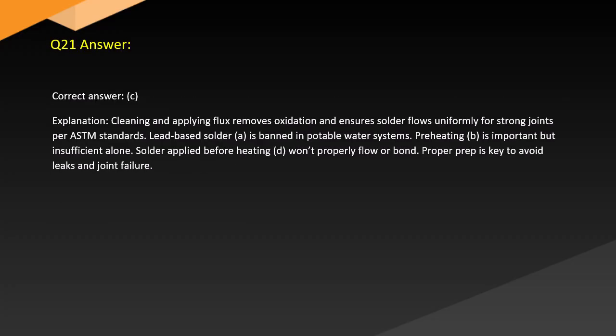Answer. Correct answer, C. Explanation. Cleaning and applying flux removes oxidation and ensures solder flows uniformly for strong joints per ASTM standards. Lead-based solder, A, is banned in potable water systems. Preheating, B, is important but insufficient alone. Solder applied before heating, D, won't properly flow or bond. Proper prep is key to avoid leaks and joint failure.